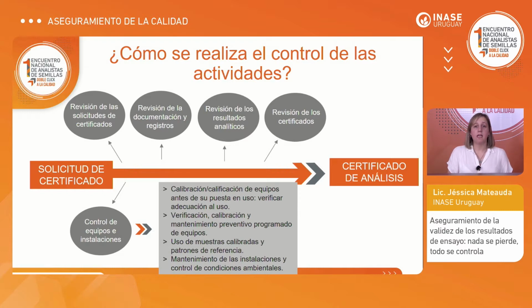To control the equipment and facilities: equipment is critical too, to assure the validity of the results of the test. So before starting to use an equipment, we have to check that it is proper for the use we want to make of it. So we have to calibrate it.